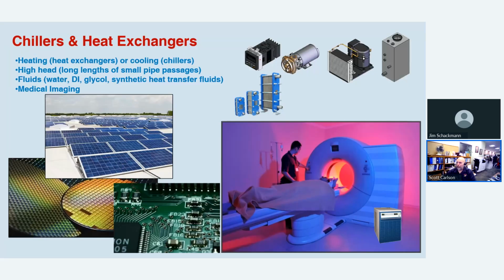Next, we have chiller applications. Because our pumps are compact, a lot of chiller manufacturers like to use them because they fit inside of their chiller, which is this small unit. It actually can control the temperature of specific pieces of equipment down to even 1/4 of a degree. When you have something like an MRI machine that you're trying to take a picture of somebody's brain, you want to have the lens be at its maximum focus and be able to take a consistent, clean picture. And so you need to have that temperature regulated so that there's no twisting or bending of any of the materials that are taking the picture.